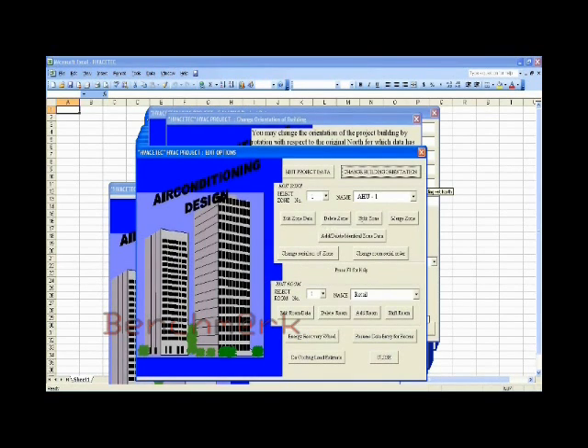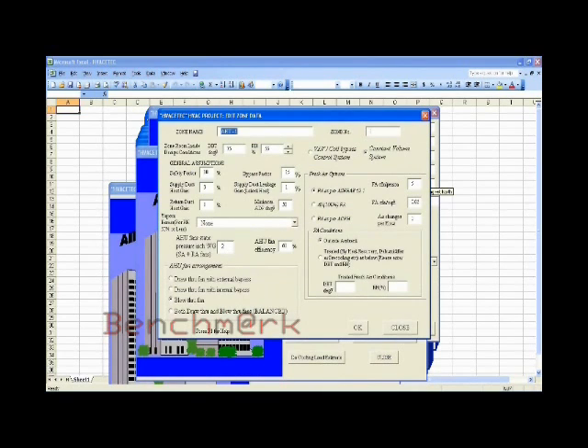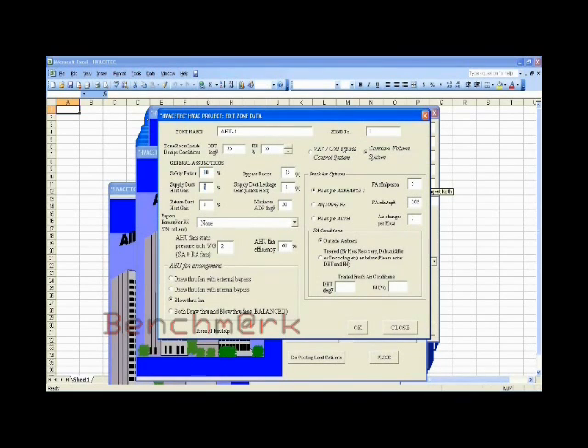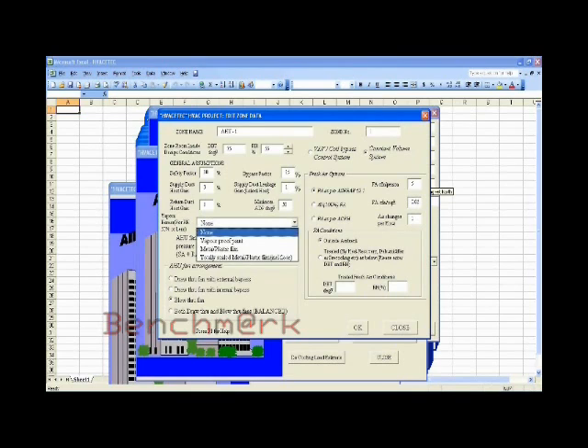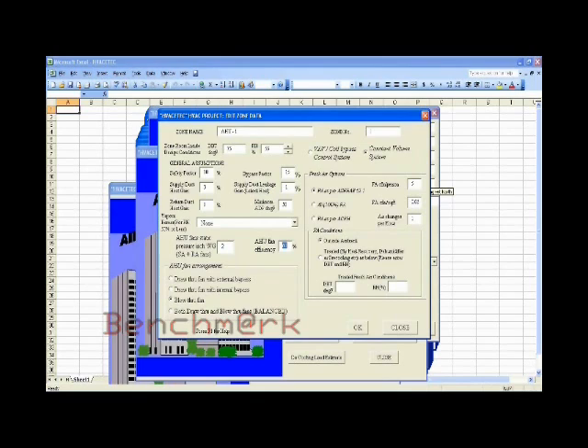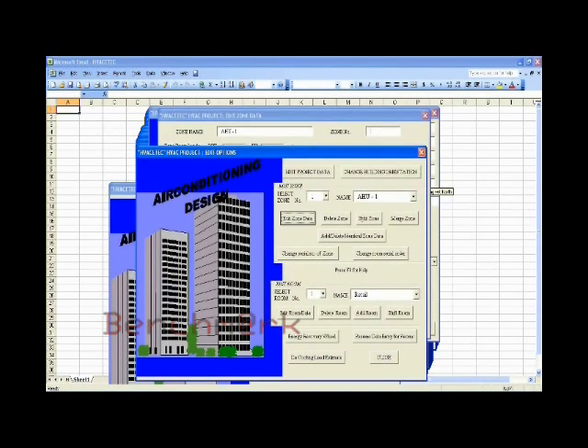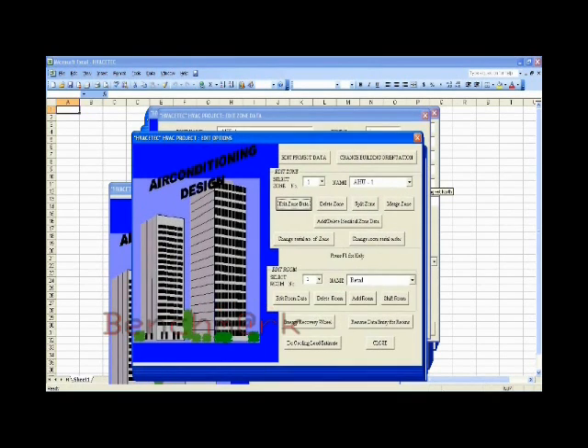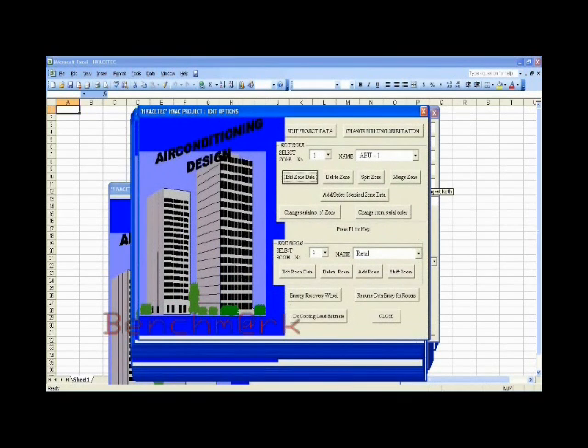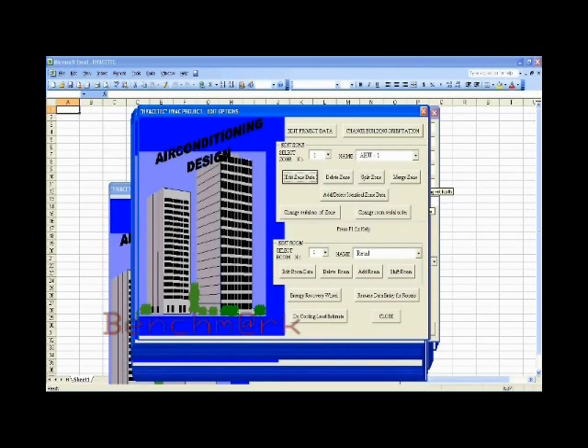Let us start with our project. Zone name: AHU-1. Indoor condition: 75°F and 55% RH. We are considering safety factor 10%, supply duct 3%, 1%. We are considering blow through type fan with one correction. What we have seen in our earlier series of Part 1: blow through type fan.